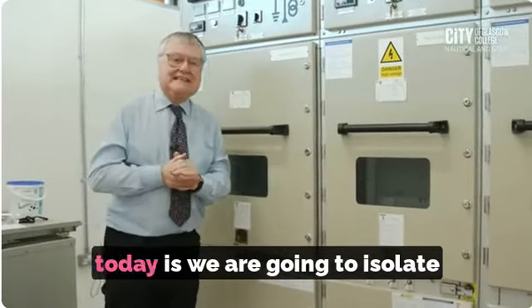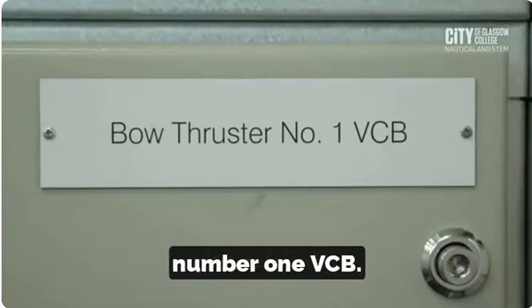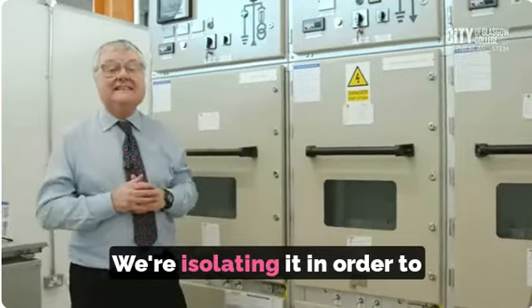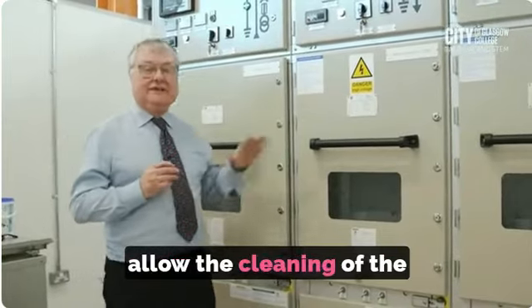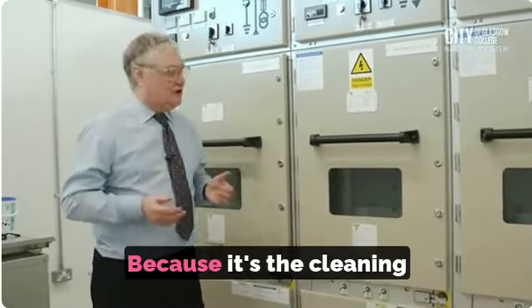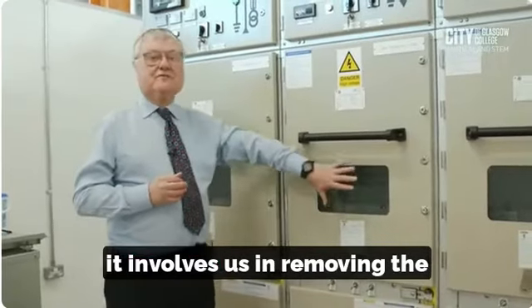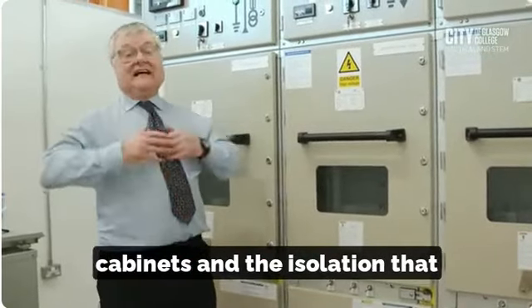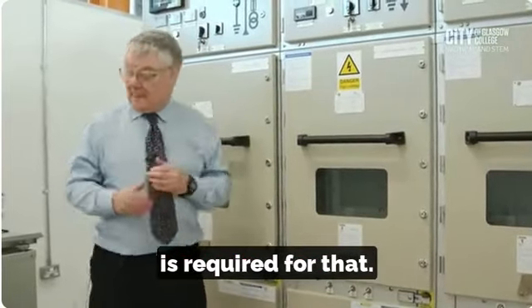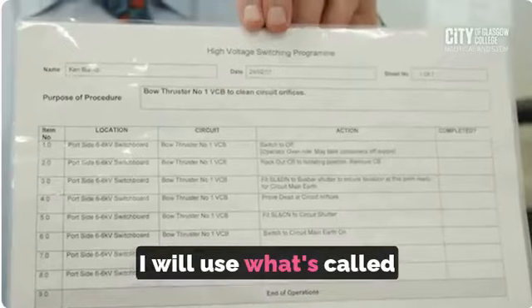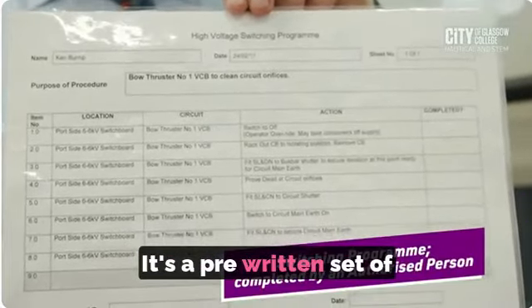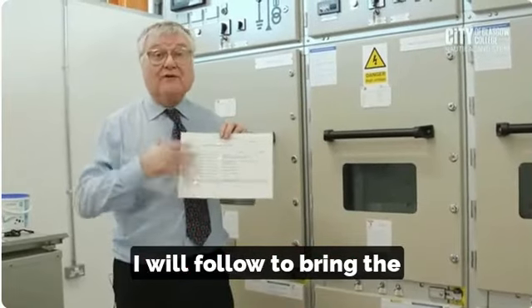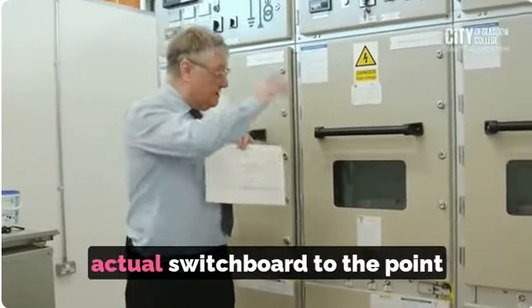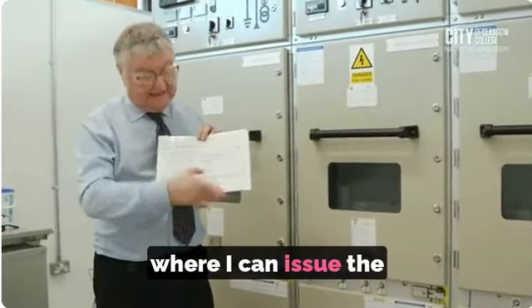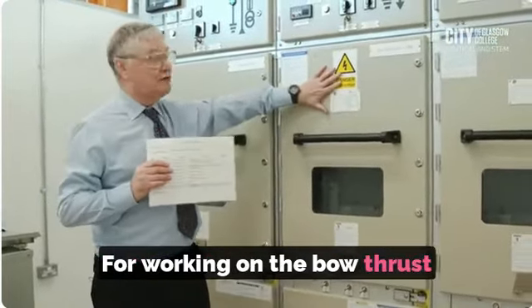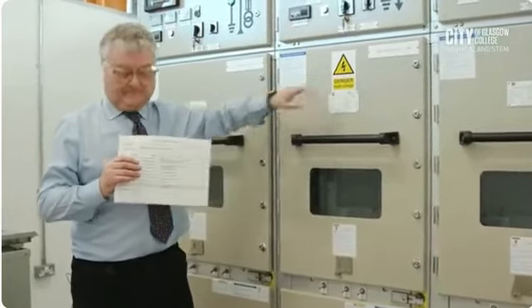The job that we're going to do today is to isolate the bow thruster number 1 VCB. We're isolating it in order to allow the cleaning of the circuit orifices. Because it's the cleaning of the circuit orifices, it involves us in removing the actual circuit breaker from the cabinet and the isolation that is required for that. To do this, I will use what's called a switching program. It's a pre-written set of chronological instructions which I will follow to bring the actual switchboard to the point where I can issue the permit to work for working on the bow thrust number 1 VCB orifices.